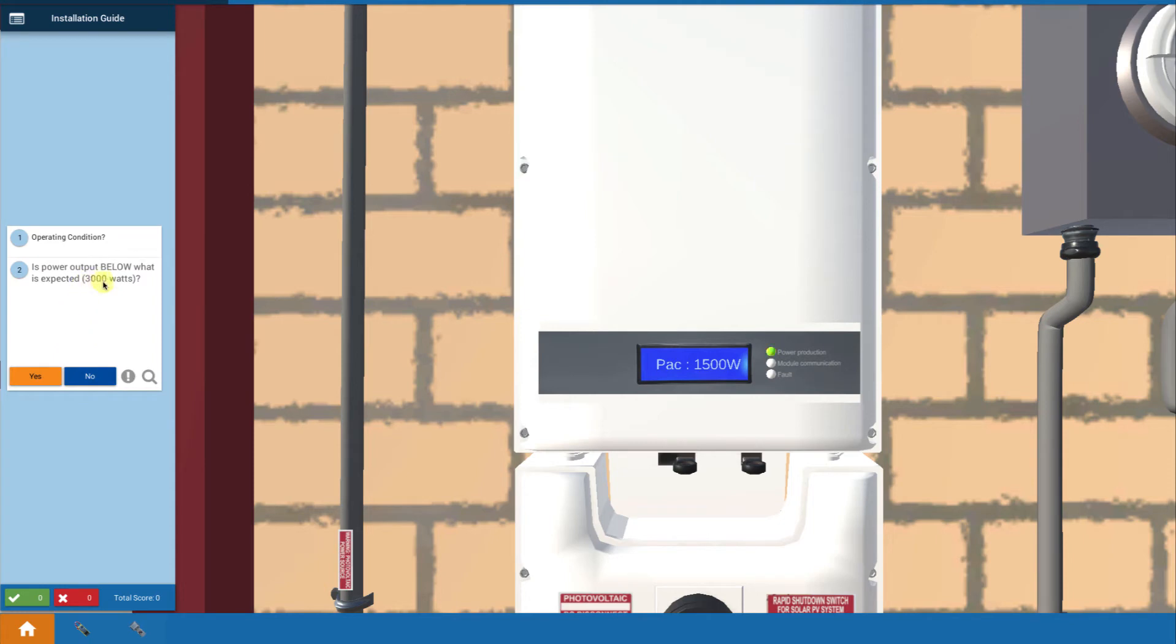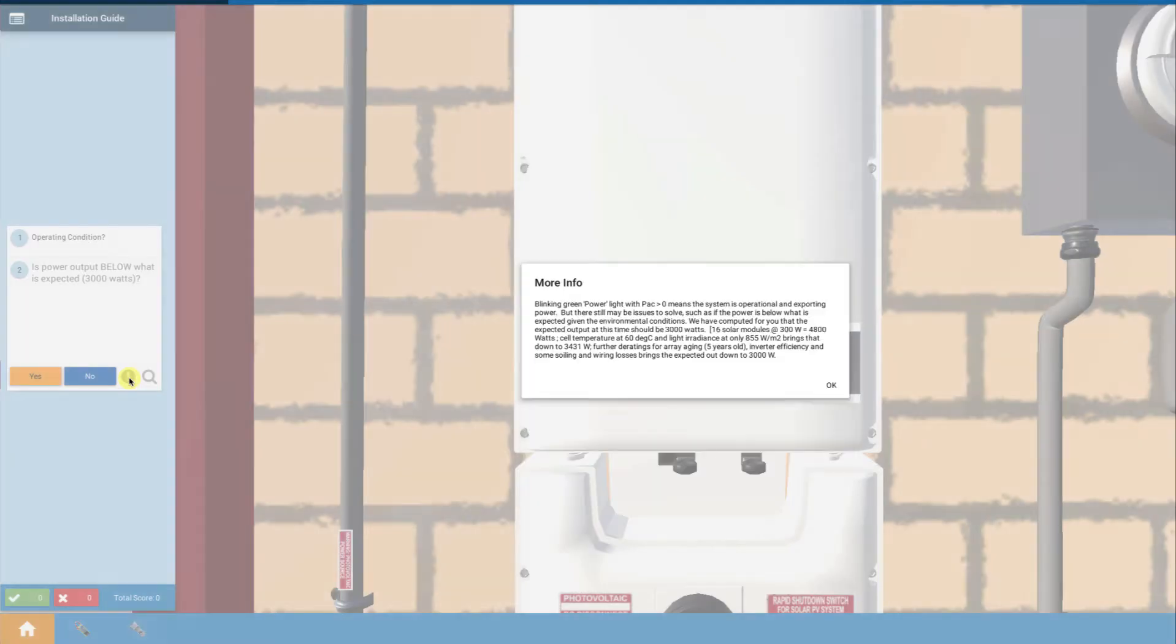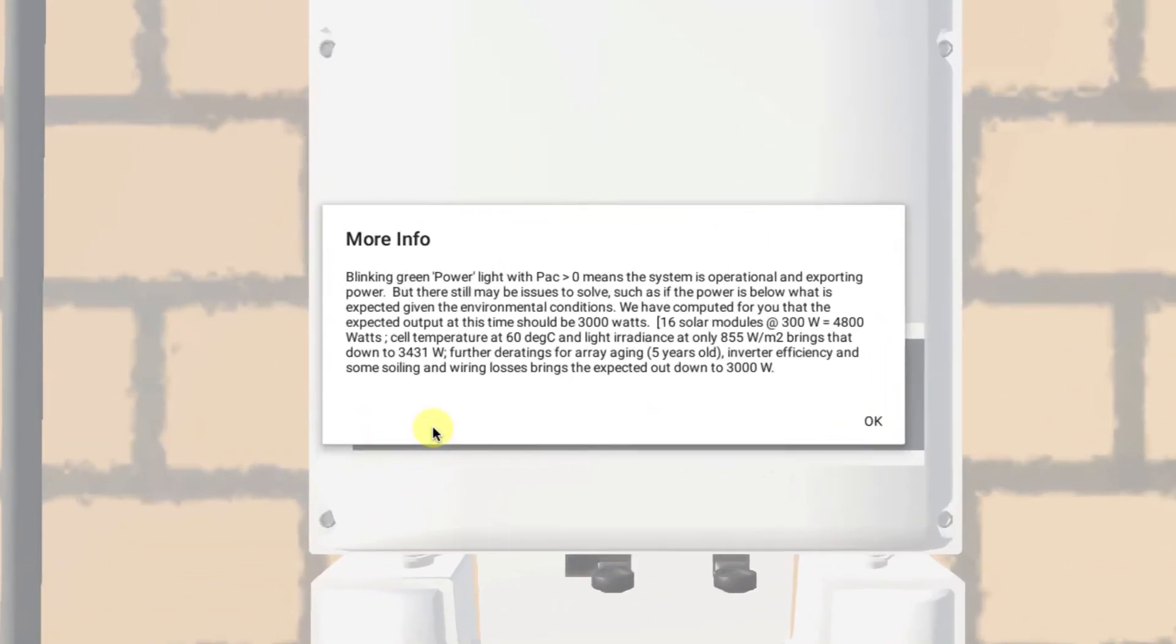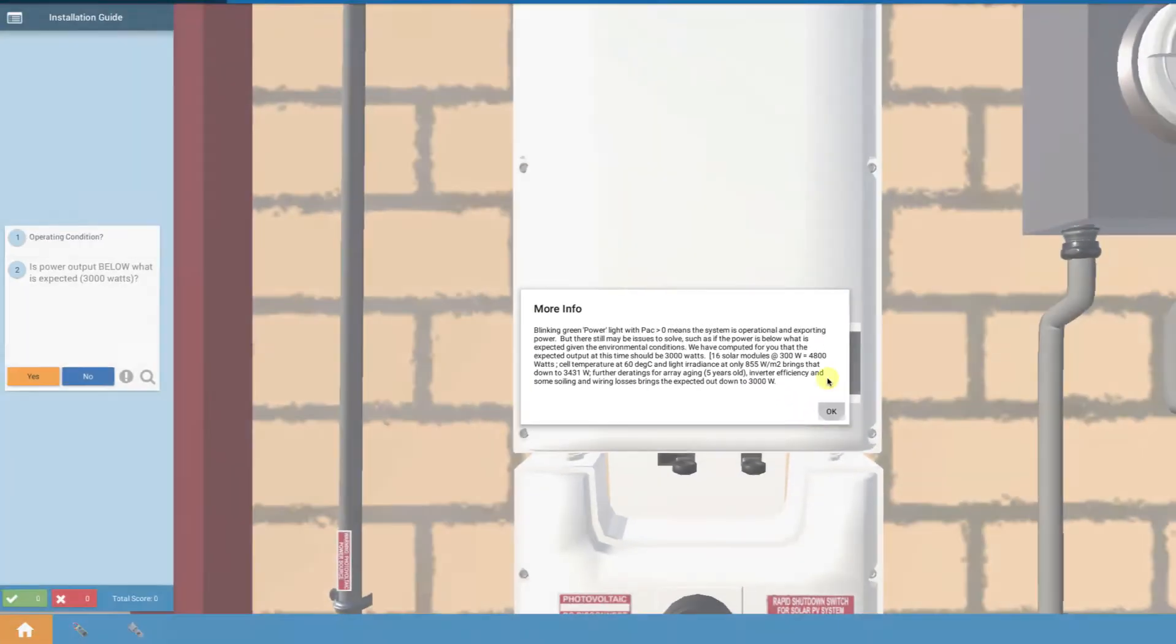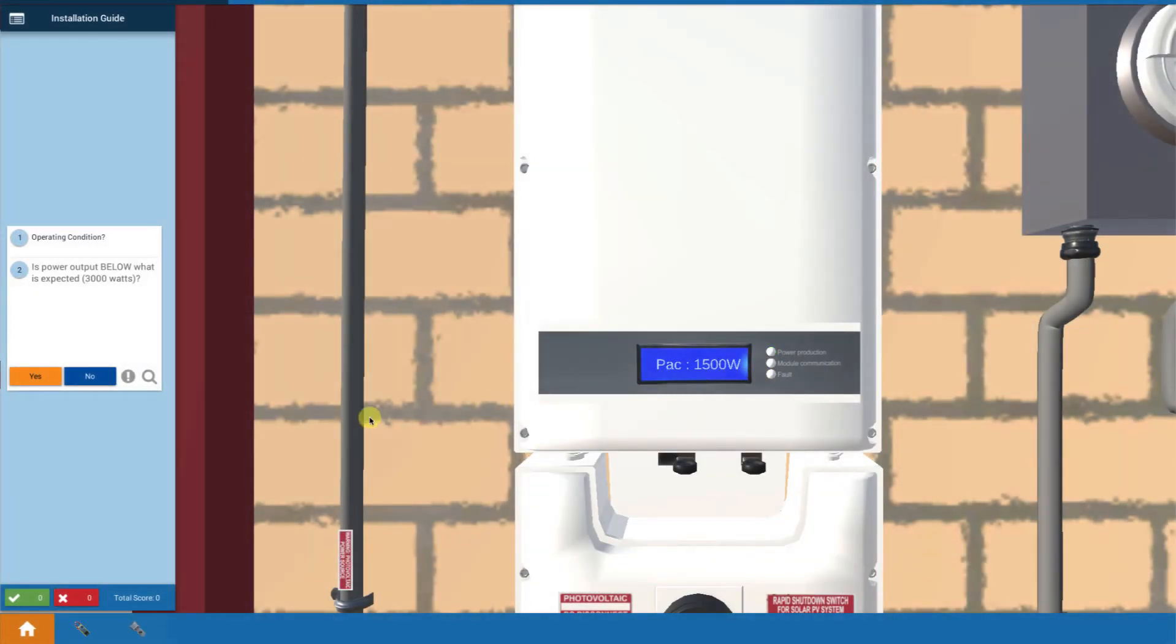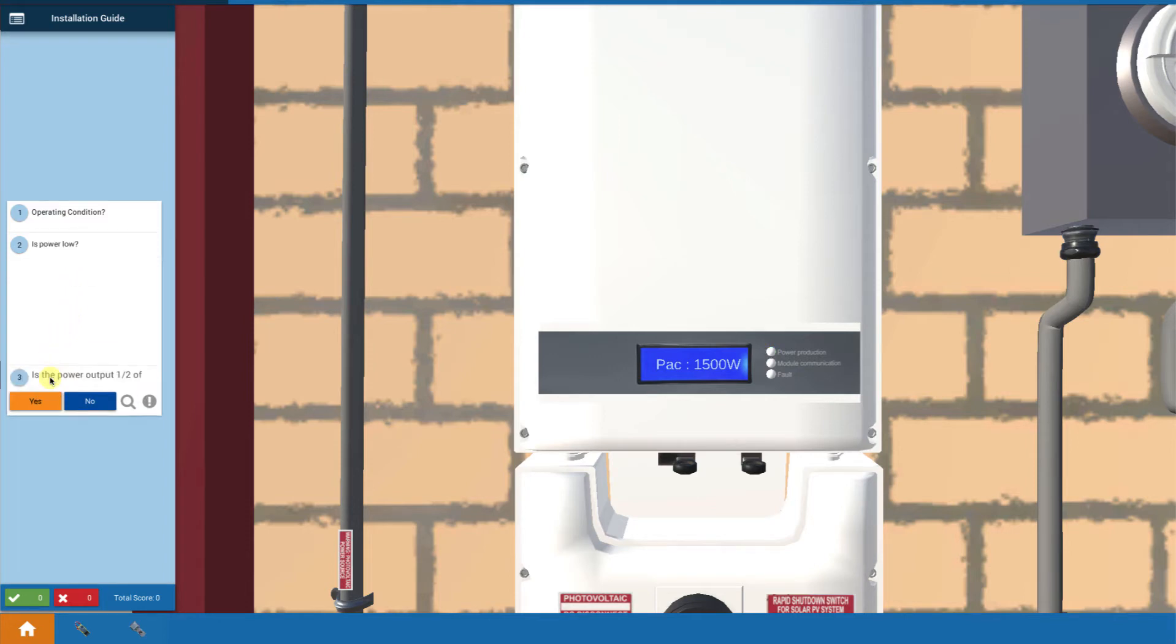But is the power below 3,000? Yes, it's only 1,500. From the site information, we should calculate that we expect about 3,000 watts from this system, but we're only getting 1,500. The power is low, so now we've got something to troubleshoot.